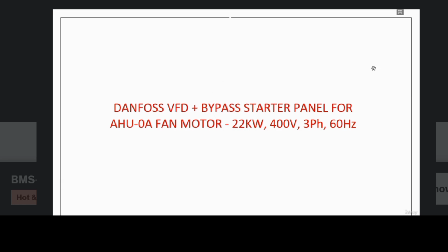In this video, we will learn to read the drawing of an MCC panel. Also, we will see how we can make connections of BMS points inside the MCC panel. This MCC panel drawing is for control of an AHU fan using a VFD and a bypass star delta circuit. The primary starter circuit is the VFD, while we also have a star delta circuit for standby in case there is a failure on the VFD, so that we can run the fan using the bypass star delta circuit.